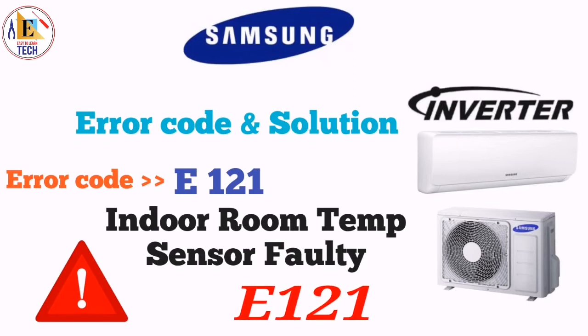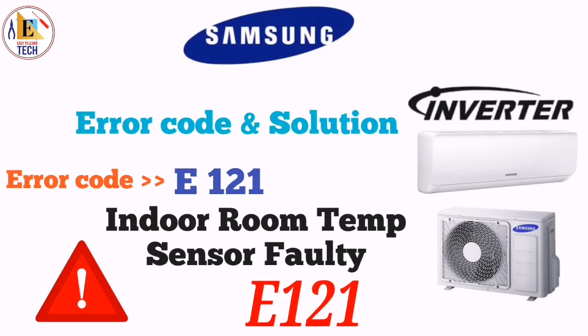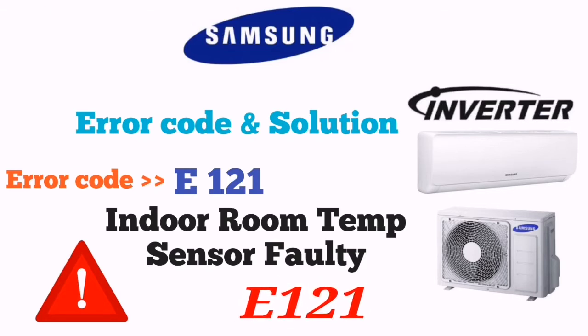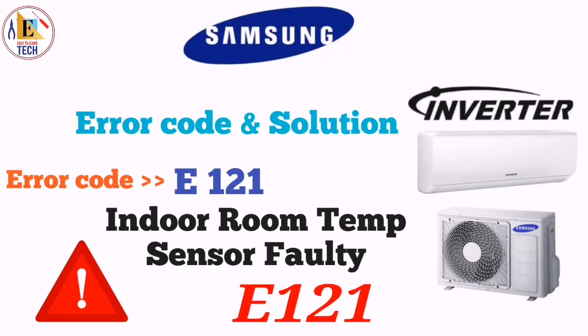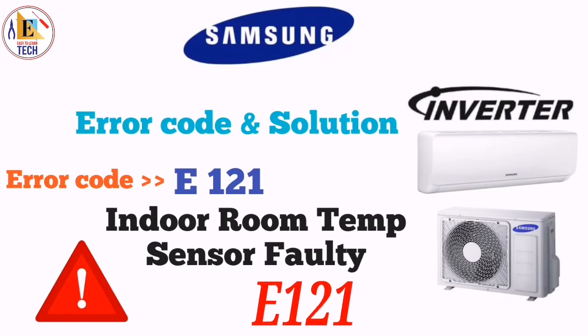Remove the connector from the PCB, give the power supply to the indoor unit, and check the voltage of #1 and #2 in the connector. Both should be above 0.5 volt or below 4.5 volt. If it is not between 0.5 volt and 4.5 volt, it means our indoor PCB is faulty. Change the indoor PCB.